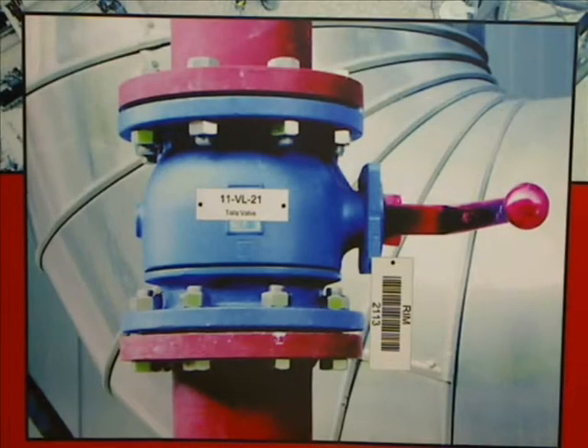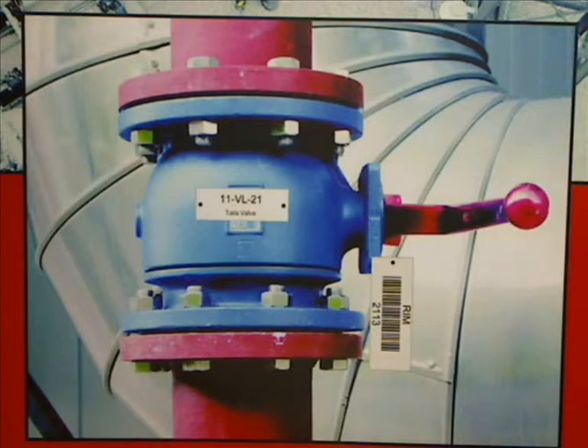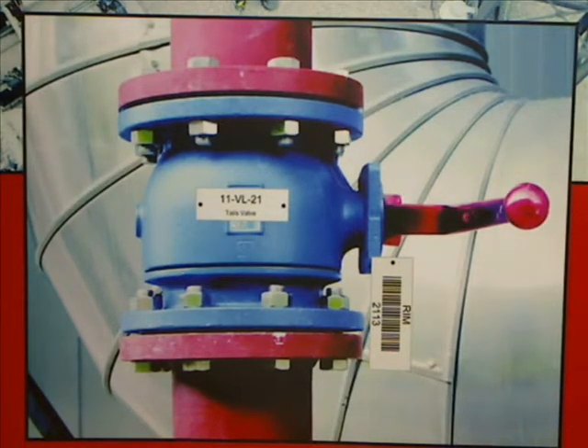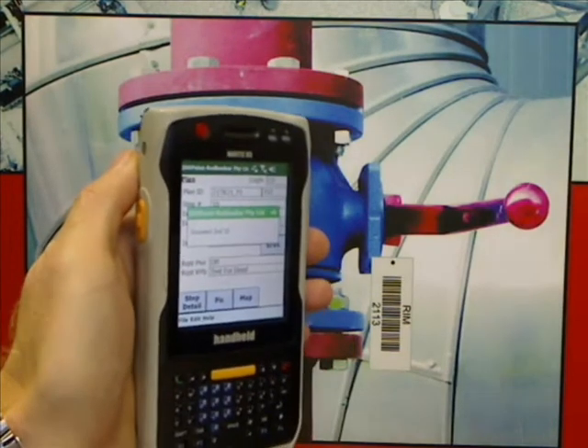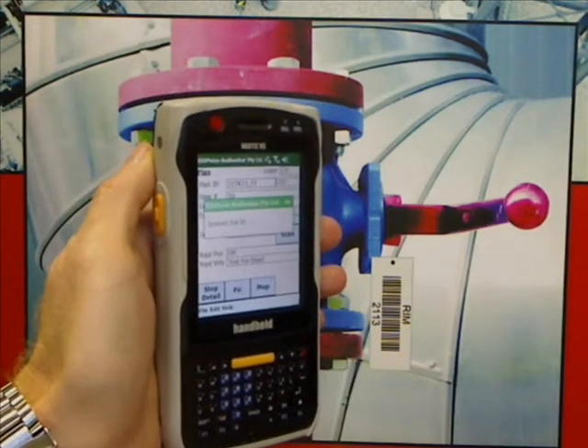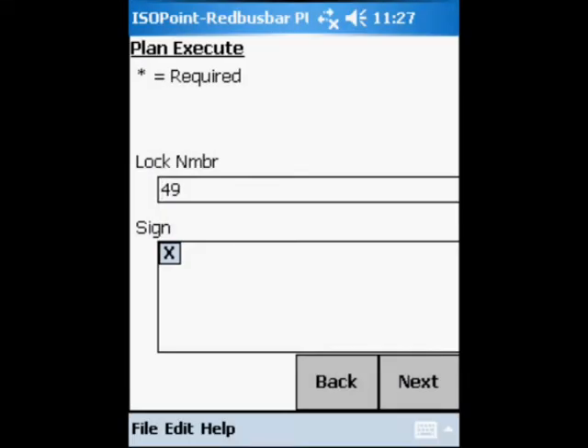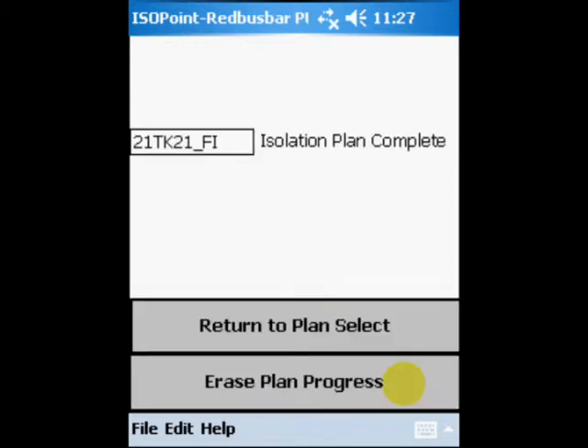The third step is to isolate 11VL22. In the event that the wrong isolation point is scanned, for example 11VL21, the PDA alarms this fact to the isolation officer with a message stating incorrect secondary ID. The PDA will not advance until the correct isolation point is scanned.